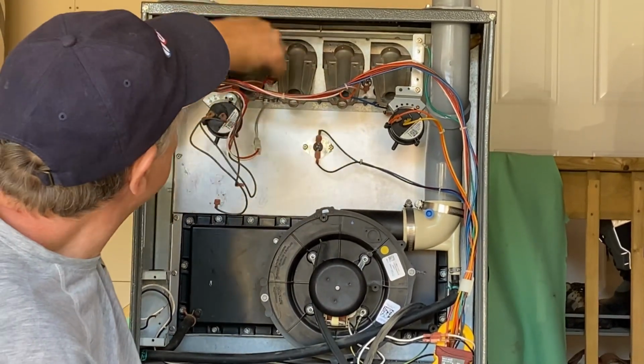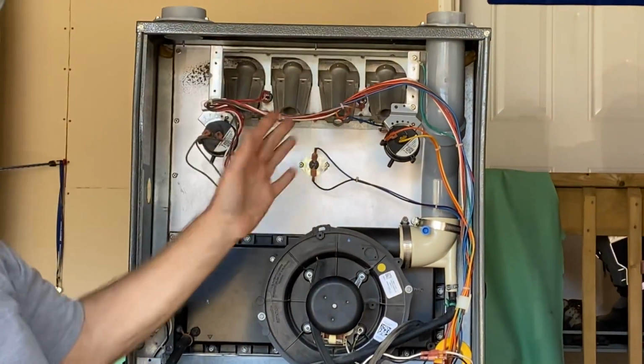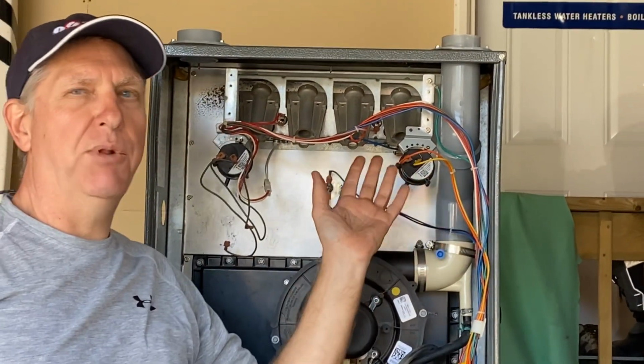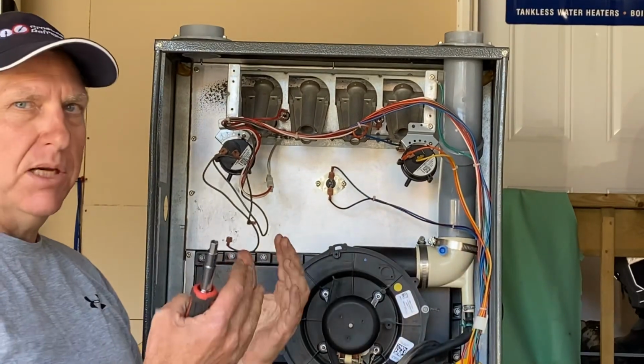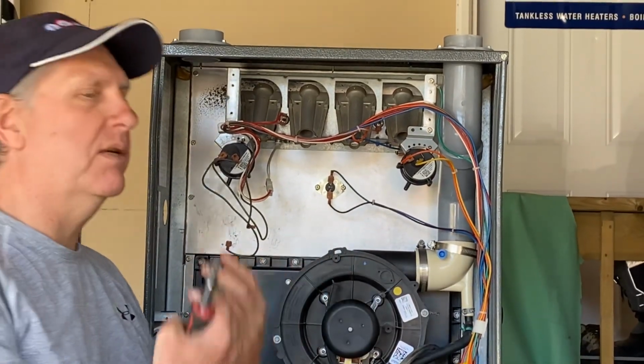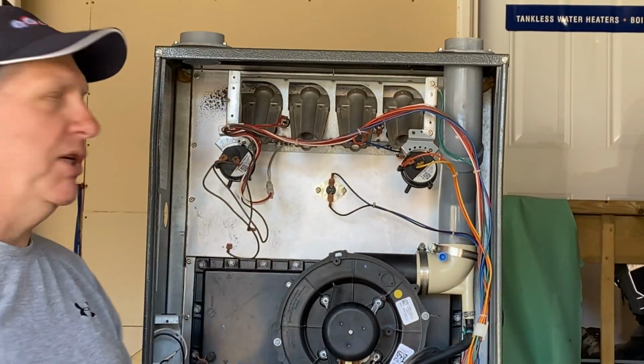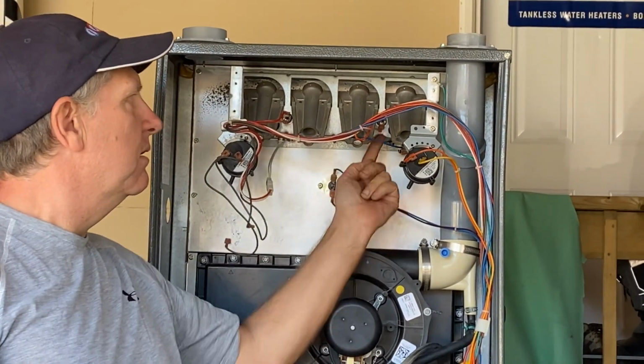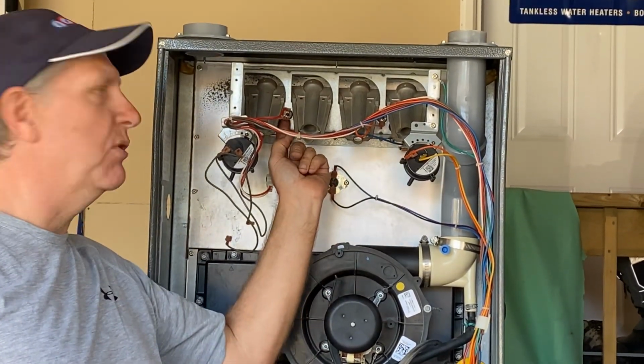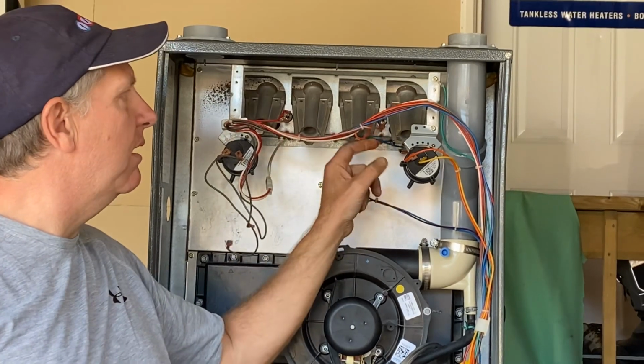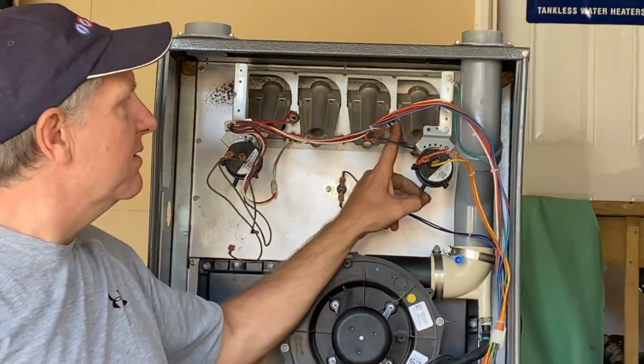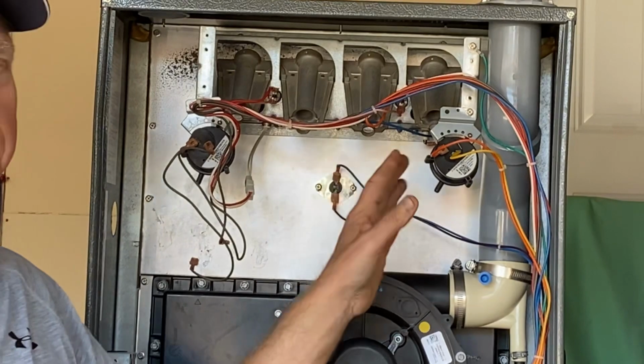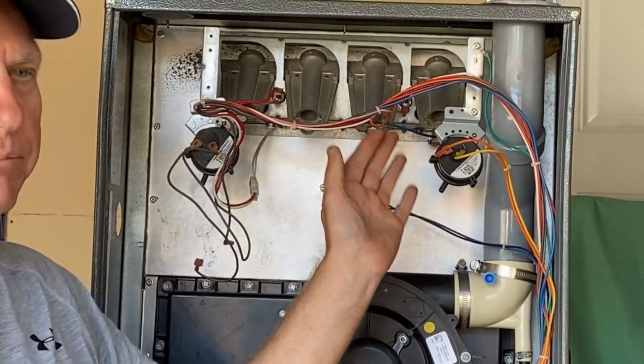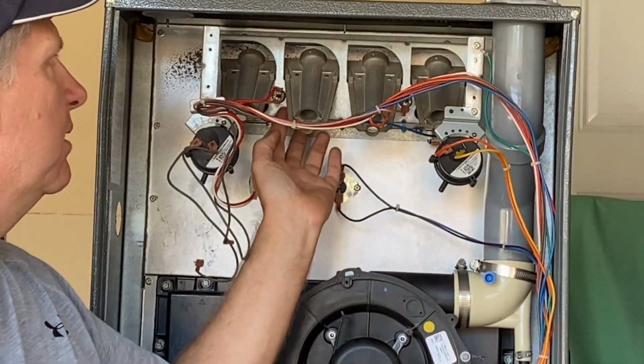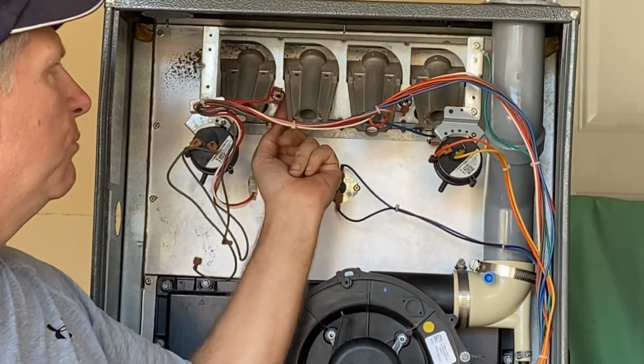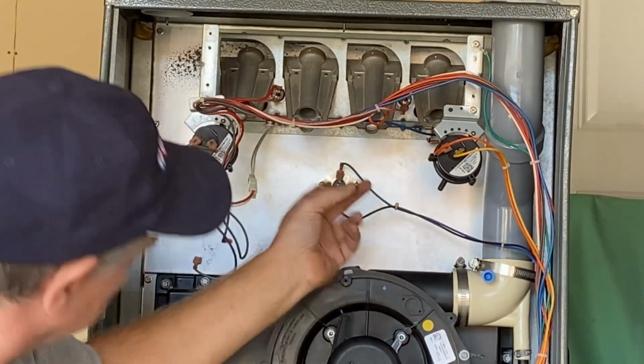The limit switches, again, 2 limit switches here. If for some reason the burners are plugged, flame starts coming back towards the front of the burner instead of going through the heat exchanger. These limit switches sense that and they will trip. They are resettable. There's a little button on them that you can press to reset it. You don't want to be pressing the button over and over and over again. If they trip, there's a reason that they trip. Those are like flame rollout safety switches.